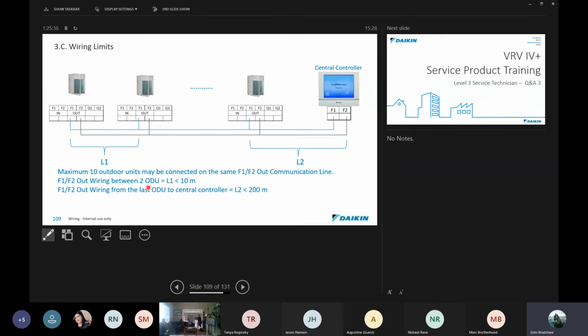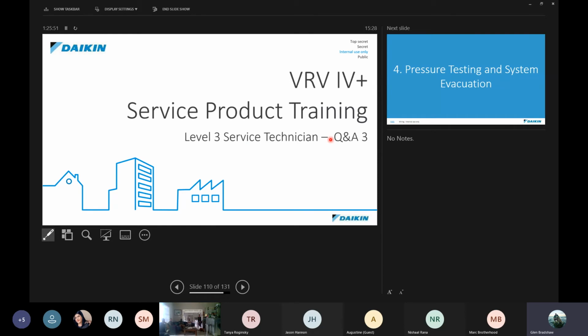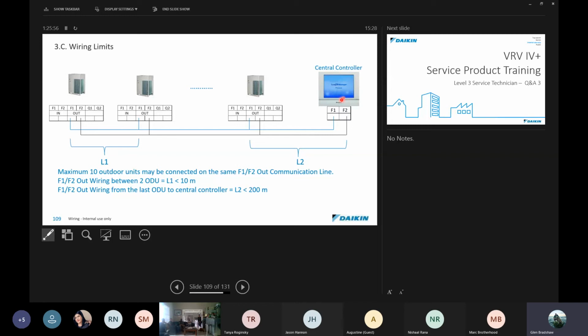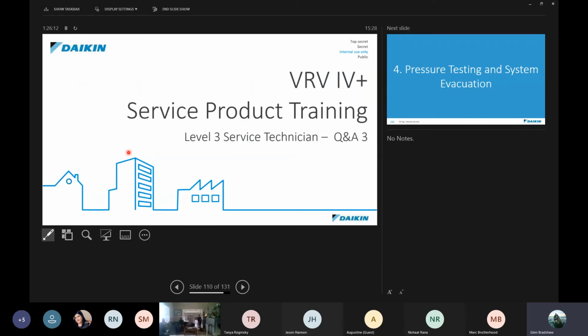Okay, and the wiring from outdoor 2, line 1, must be less than 10 meters, and from the last outdoor to the controller, less than 200 meters. Remembering that when you're doing this type of wiring, especially to centralized controllers, it is advisable, because this wiring does get long, to use a screen cable, and to remember that you always need to earth at least one side of each section of that screen cable. Just keep that in mind, because it'll save you a lot of heartache in the long run.